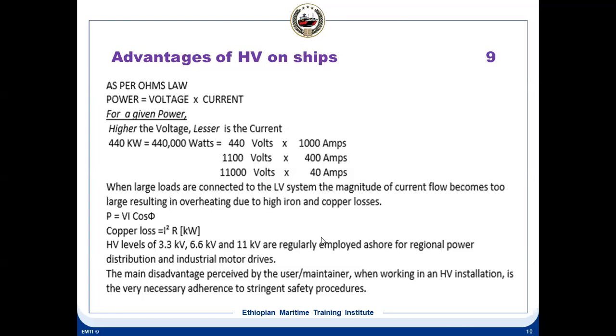So when the current is going high, what happens? Overheating, and losses are more, because of high current. Copper losses are more because copper loss is I square R. So from this it is very clear that a 440 volt system, to deliver 440 kilowatt, has to take 1000 amps. At the same time, if you increase the voltage to 11,000 volt or 1100 volt or 6,600 volt, the current rating is reduced. That's the whole advantage of using high voltage systems on ships.